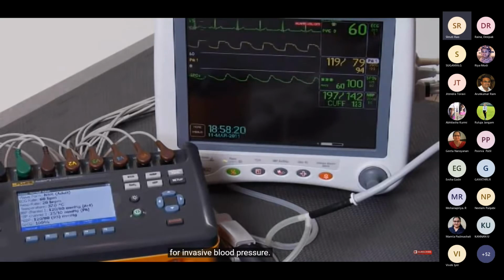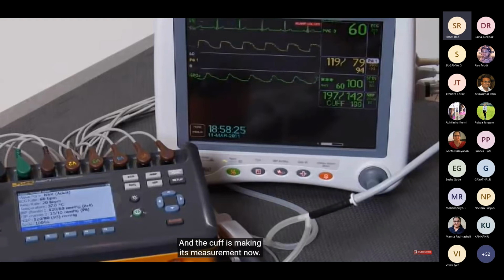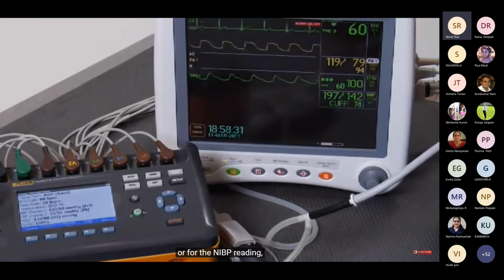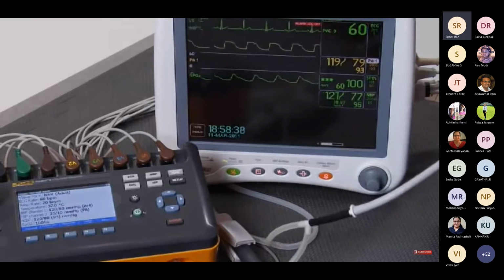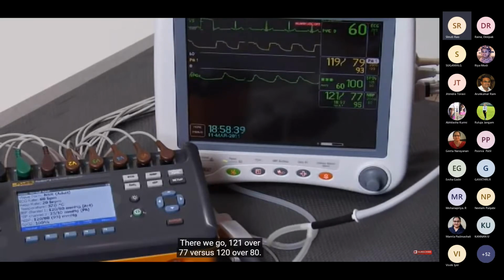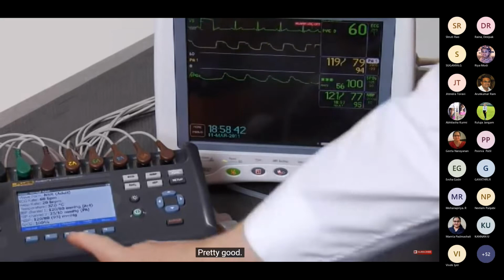And the cuff is making its measurement now for the NIBP reading. O2 sat is 100%. There we go, 121/77 versus 120/80, pretty good. We'll go to hypotensive now and start another cuff measurement.